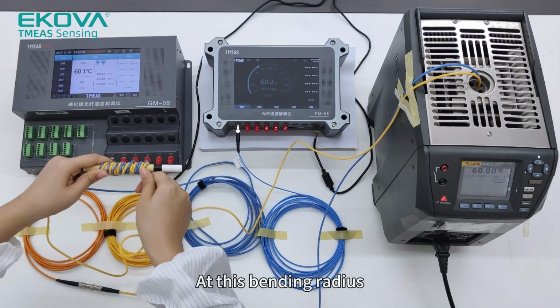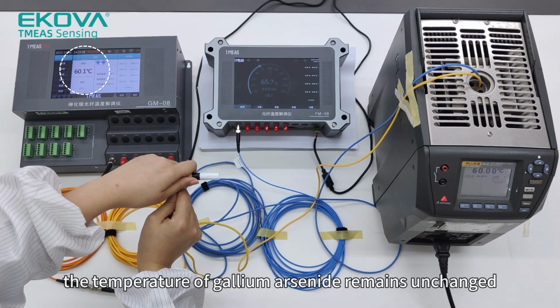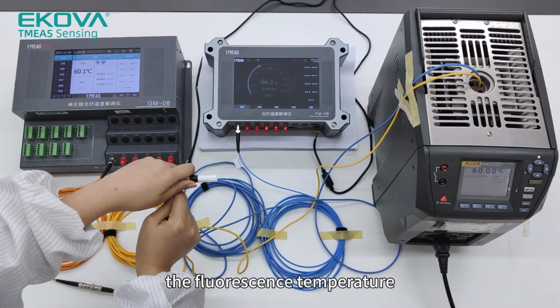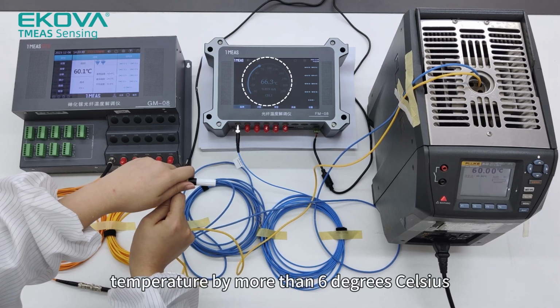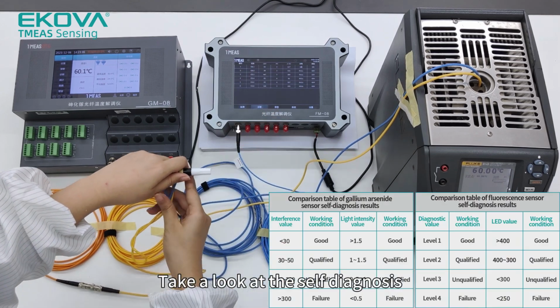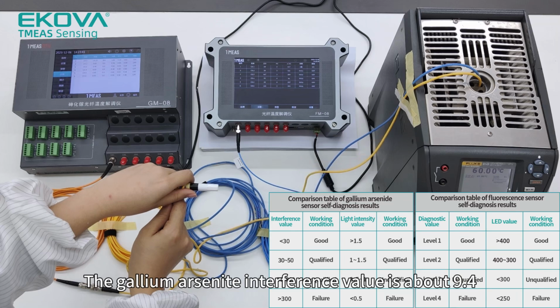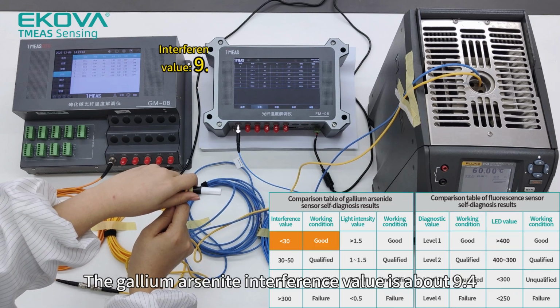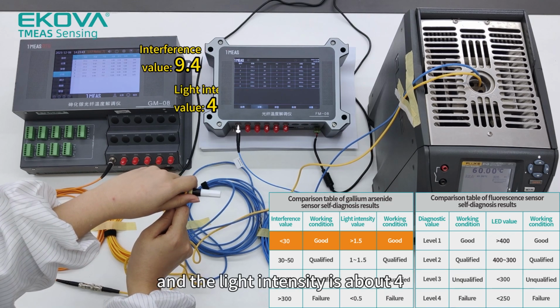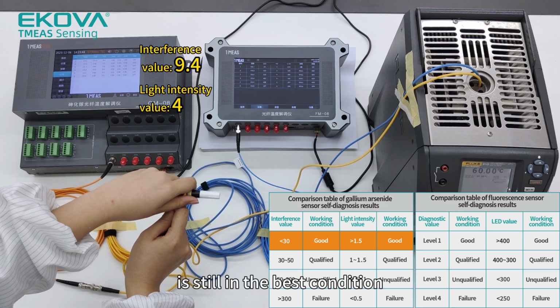Finally, a 10 mm radius round rod test was used. At this bending radius, the temperature of gallium arsenide remains unchanged. The fluorescence temperature has exceeded the actual temperature by more than 6 degrees Celsius. Take a look at the self-diagnosis. The gallium arsenide interference value is about 9.4, and the light intensity is about 4, indicating that the temperature measurement is still in the best condition.